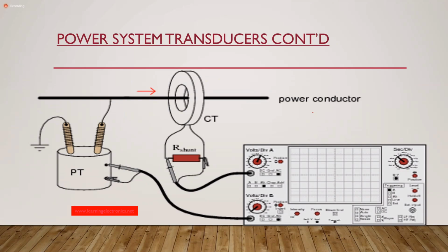And for your VT, well, obviously the fact that I have PT here tells you that this figure is a little old. But anyway, your VT is connected across. Now, the standard output for your VT is 110 volts phase to phase. All right, so it's 110 volts phase to phase. Sir, is that both for US and UK, sir? Yes. Okay, thanks. Or 63.5 volts phase to earth, or line to earth. All right, so 110.